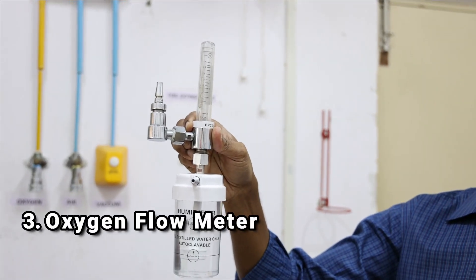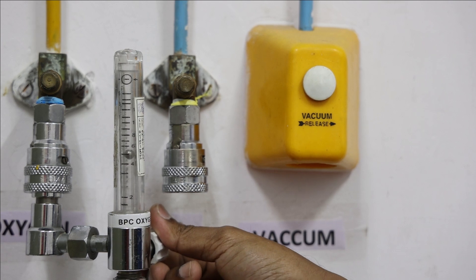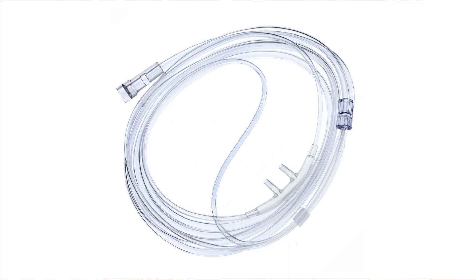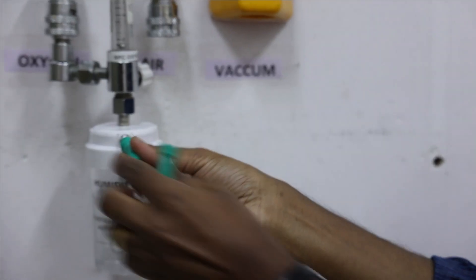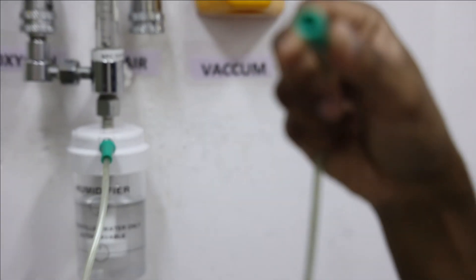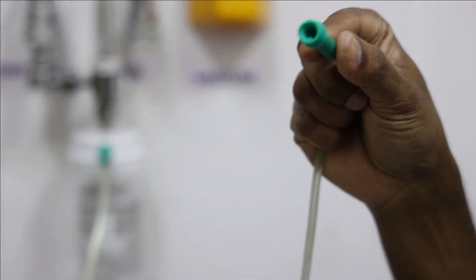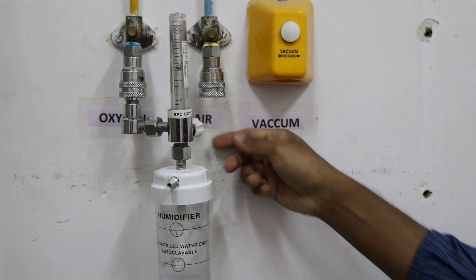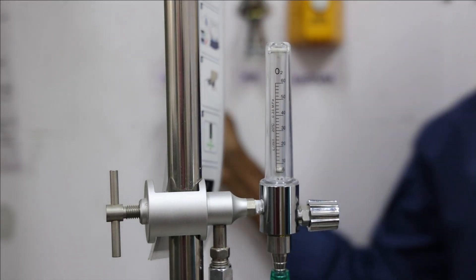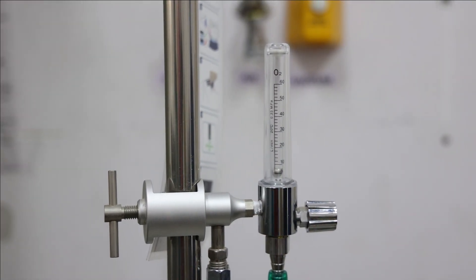The oxygen flow meter is used to provide oxygen to the patient from a terminal dispensing unit through a nasal cannula or a mask. Its primary function is to regulate the flow rate of oxygen as it passes through a humidifier. It can not only accurately measure the instantaneous flow of oxygen but can also enable healthcare workers to keep abreast of patient oxygen absorption status.